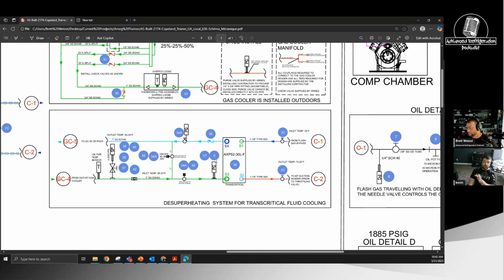No, this was actually off, it was in bypass. So we had not tested this at that point. So the bypass was open and the ball valve going into the heat exchanger was closed, so it was not flowing through the heat exchanger at all. This ball valve right here - yep, it was closed going in there.